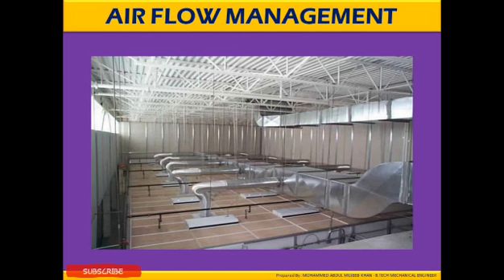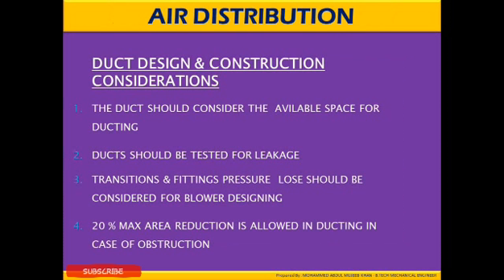Airflow management. Duct designing and construction consideration. The duct should be designed considering the available space for the ducting. Ducts should be tested for leakage. Transitions and fitting pressure losses should be considered for blower design. 20% maximum area reduction is allowed in ducting in case of obstructions.